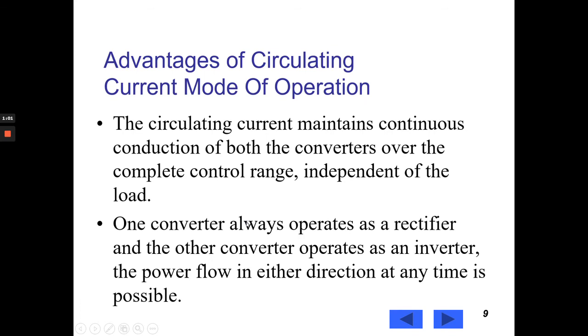Now, we will see advantages of circulating current mode of operation. The circulating current maintains continuous conduction of both the converters over the complete control range independent of the load. One converter always operates as a rectifier and the other converter operates as an inverter.